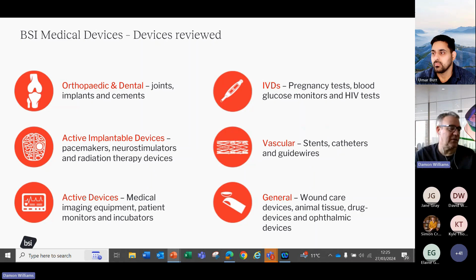So it's a risk-based classification system for medical devices. There are lots and lots of different types, and we go from class 1 low risk devices up to class 3, which are high risk devices. Class 1 devices would be a wound dressing like a bandage or a plaster, pretty low risk. If it doesn't work properly, it's not really going to cause much damage. You just get a different one and try again. Then class 2A is low to medium risk. A syringe with a needle is slightly more risky than a bandage because the needle could snap off or maybe something could go wrong there.